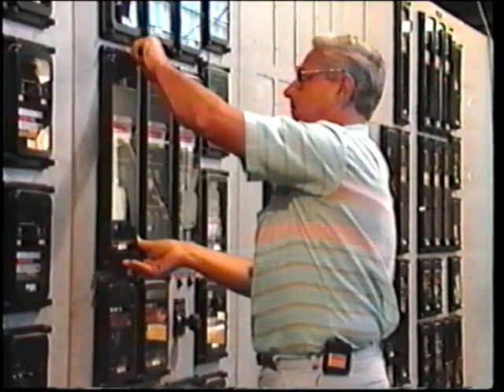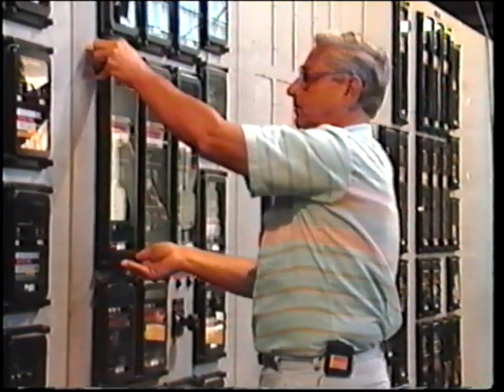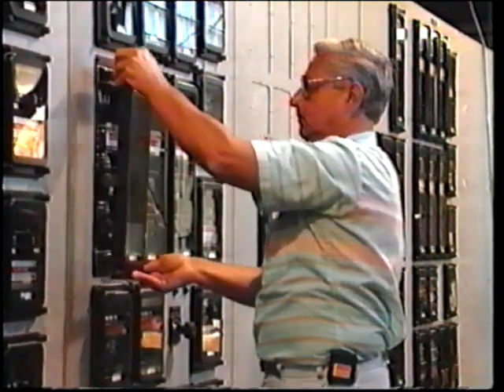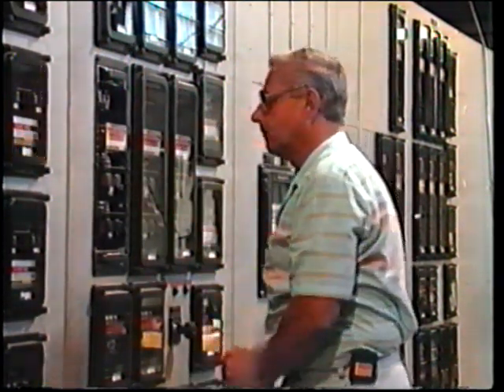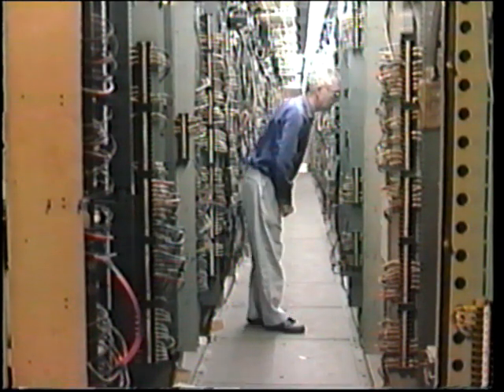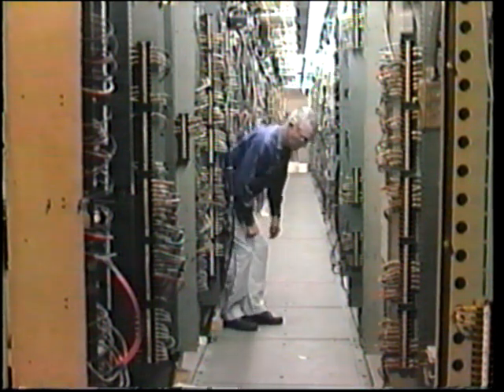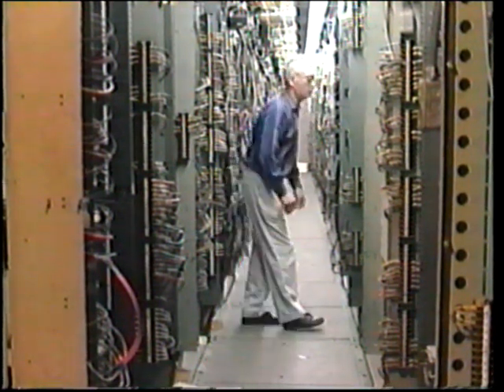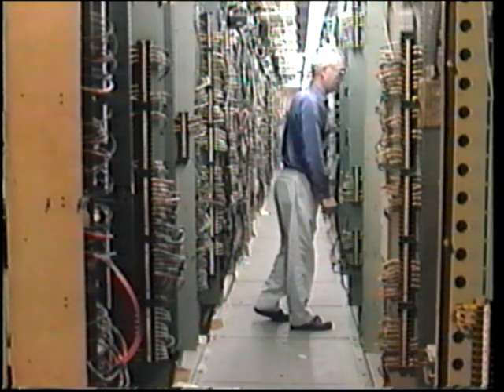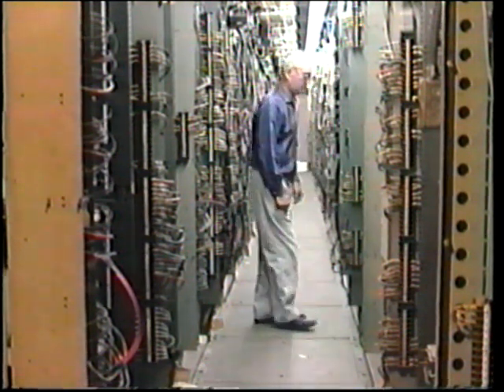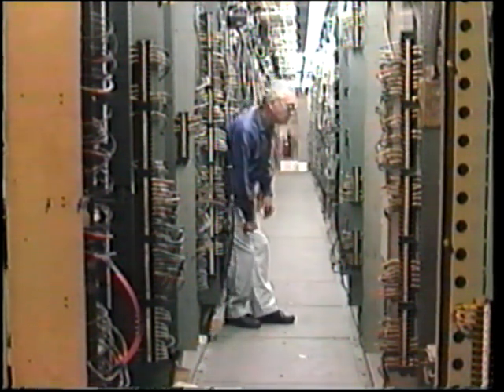And here is another case involving relay covers, but with a difference. One relay technician was working in front of the panel while his companion was behind, observing operation of the relays. Within the vicinity, there were several live relays without covers, and he inadvertently brushed against one of these, causing tripping of a bus section. It is true that the technician should have taken more care, especially as protective covers were not on all the relays.